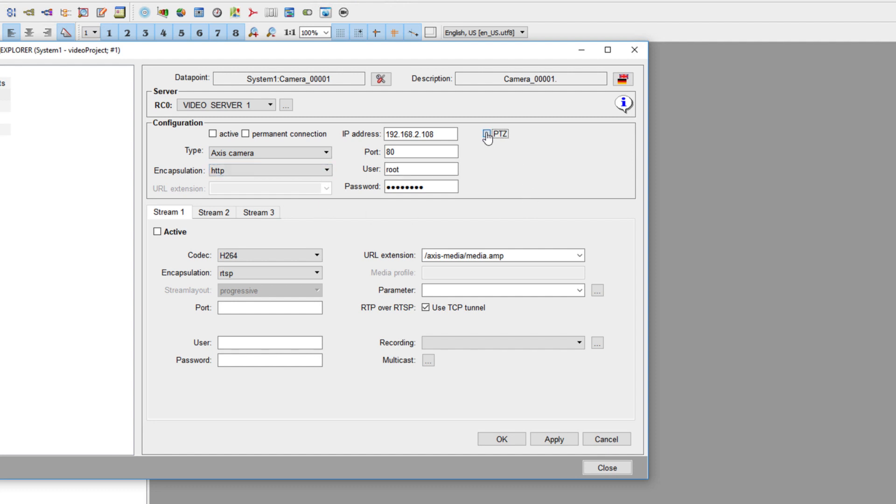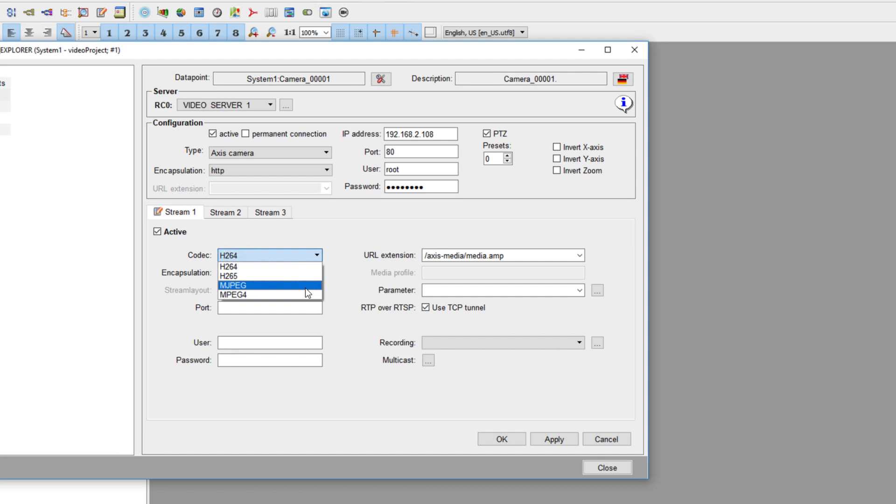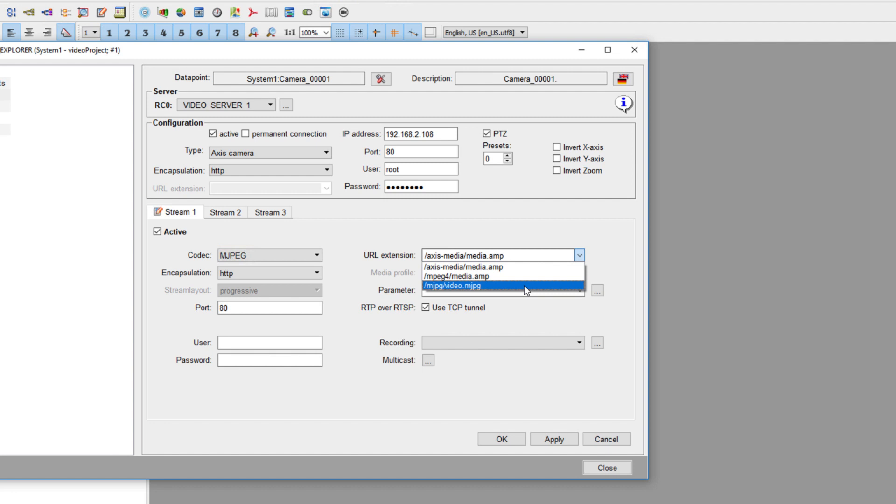This camera has pan tilt zoom functionality, so I'm going to check box that I want to make it active. Then I want to make it a permanent connection. This allows you, if you're on the screen, it's going to keep it there. Or I can say I want this camera always streaming to the system. It doesn't need to be a permanent connection in this particular instance I'm showing. I'm going to pick stream one, make it active, and use the MJPEG type. I am using HTTP, it's going through port 80. We're using a TCP tunnel. I'm adding my username and password of the device once again, and I'm going to hit apply.